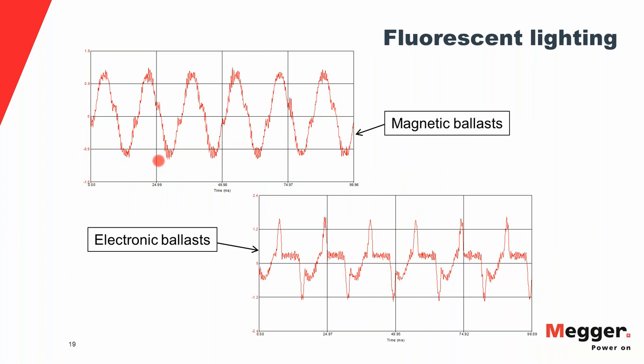Another harmonic source is fluorescent lighting. Fluorescent lights are discharge lamps: gas inside the lamp requires an initial high voltage to cause a discharge, after which current must be limited by a ballast. There are two types of ballast: magnetic ballast (using an iron-core transformer and capacitor) and electronic ballast (employing a switch mode power supply circuit with switching). The type of ballast has significant influence on current waveform distortion — there is much more distortion with electronic ballast.